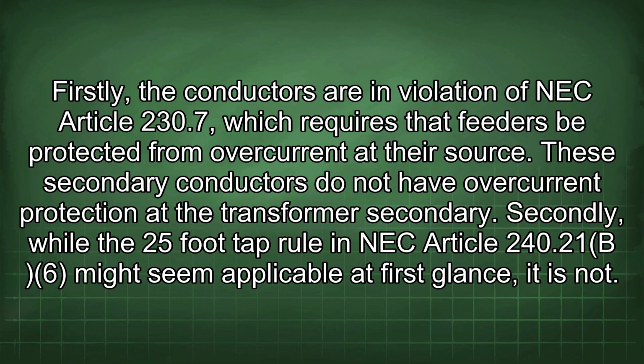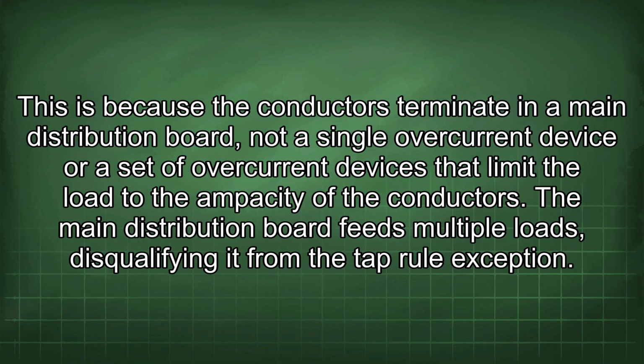Secondly, while the 25-foot tap rule in NEC Article 240.21(B)(6) might seem applicable at first glance, it is not. This is because the conductors terminate in a main distribution board, not a single overcurrent device or a set of overcurrent devices that limit the load to the ampacity of the conductors. The main distribution board feeds multiple loads, disqualifying it from the tap rule exception.